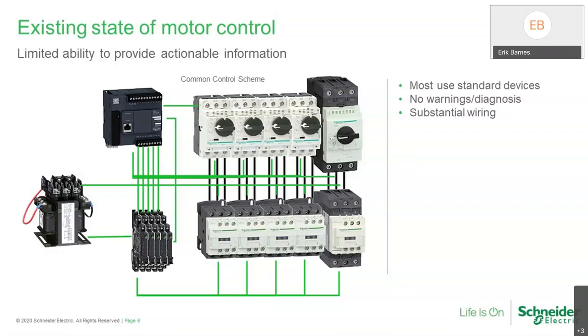So now they shut things down, open the panel up, and see what's going on. They trace it and find the overload protection device is in a trip state. Now, why did it trip? Was it an overload condition, too much load for the motor? Was it a phase imbalance condition? Was there a jam somewhere? Jams will create an overload trip. There are a lot of scenarios, and they really don't know what's going on, so now we've got to do further investigative work.